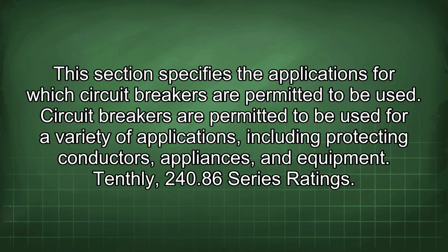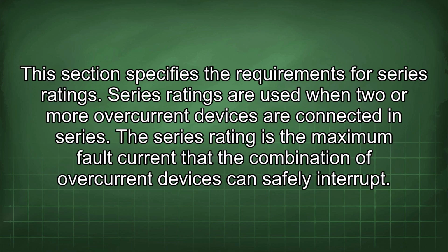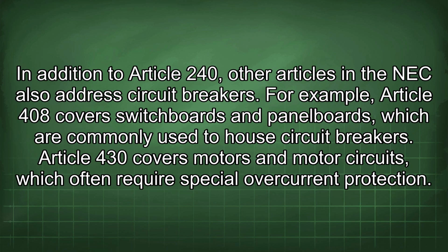Tenthly, 240.86 Series ratings. This section specifies the requirements for series ratings. Series ratings are used when two or more overcurrent devices are connected in series. The series rating is the maximum fault current that the combination of overcurrent devices can safely interrupt. In addition to Article 240, other articles in the NEC also address circuit breakers. For example, Article 408 covers switchboards and panel boards, which are commonly used to house circuit breakers. Article 430 covers motors and motor circuits, which often require special overcurrent protection.